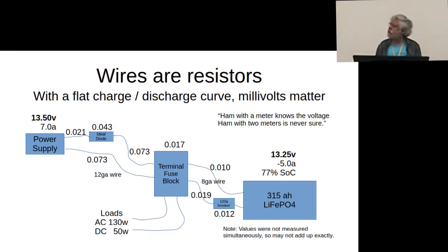But look at those other numbers: 0.021, 21 millivolts of drop across about an 18-inch piece of wire. 73 millivolts between the diode and the terminal block. I'm losing some current here, losing power, but mainly you can't tell—the curve is so flat. These millivolts make a difference. Your connections make a big difference.